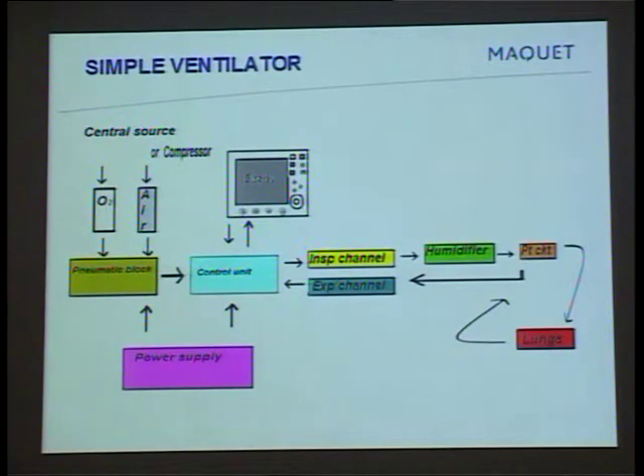Now I am showing a simple block diagram of a ventilator: how exactly the ventilator will look and what components will be inside the machine. I am showing only the block diagram, not all the components of the equipment. We are giving pressure as a source. Most hospitals will have a central source of air and oxygen, or some hospitals will have only the oxygen source, without air. So why both air and oxygen? The machine can work if you give simple oxygen also. With the oxygen pressure also it will work.